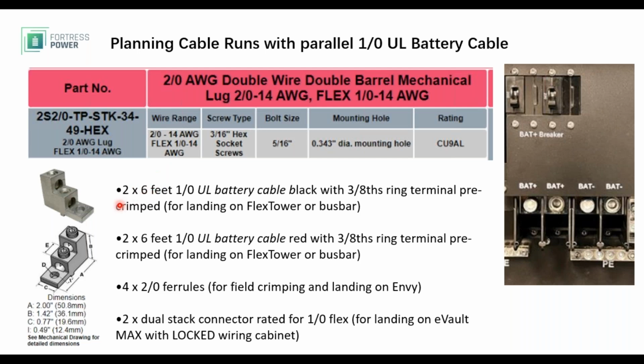You know, these ports support 1-aught all the way to 3-aught cable connection. So that could definitely be a possibility when connecting one inverter to one eVault MAX. You would use this lug right here.